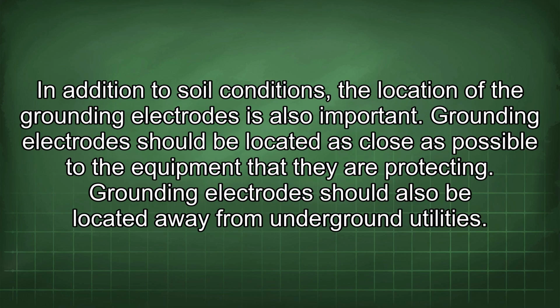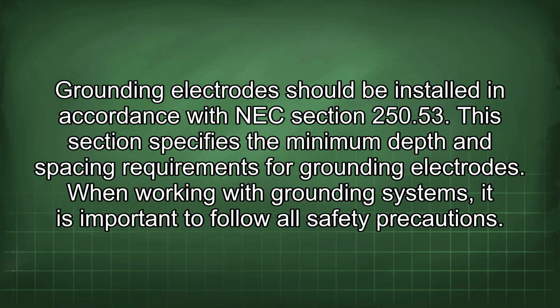In addition to soil conditions, the location of the grounding electrodes is also important. Grounding electrodes should be located as close as possible to the equipment that they are protecting. Grounding electrodes should also be located away from underground utilities. Grounding electrodes should be installed in accordance with NEC section 250.53. This section specifies the minimum depth and spacing requirements for grounding electrodes.